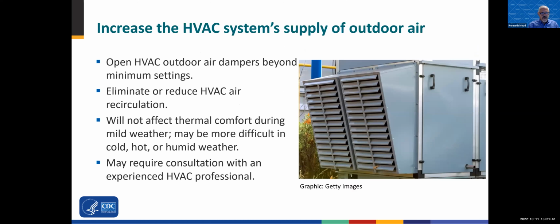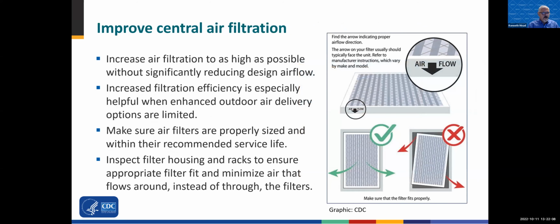You can add outdoor air through your HVAC system by adjusting the outdoor air dampers. In most scenarios, you use this tool to eliminate or reduce HVAC air recirculation. It's not going to affect thermal comfort during mild weather. It's going to be a little more difficult during hot, cold, or humid weather, and may require HVAC consultation in those scenarios, especially in very cold weather. You do not want to freeze your coils.